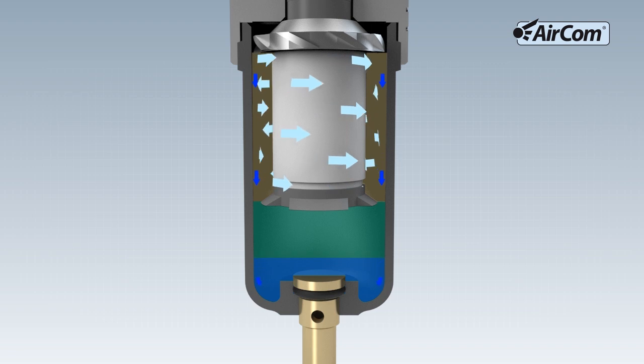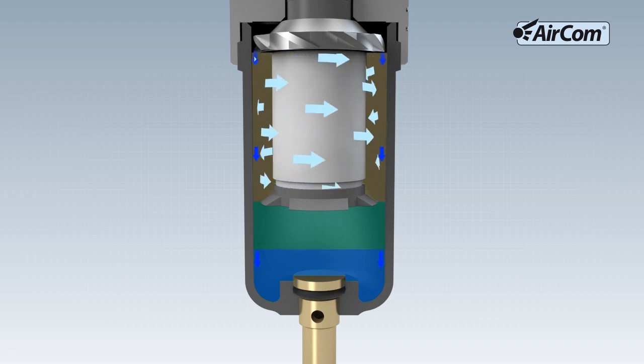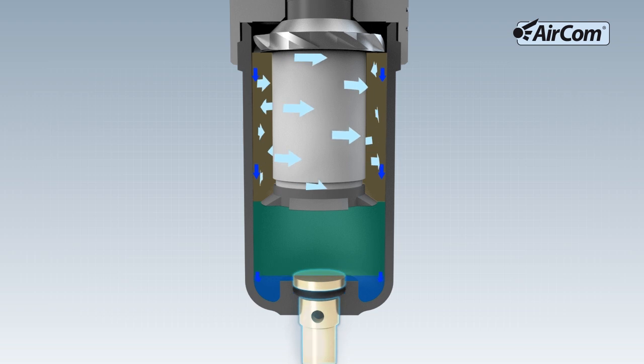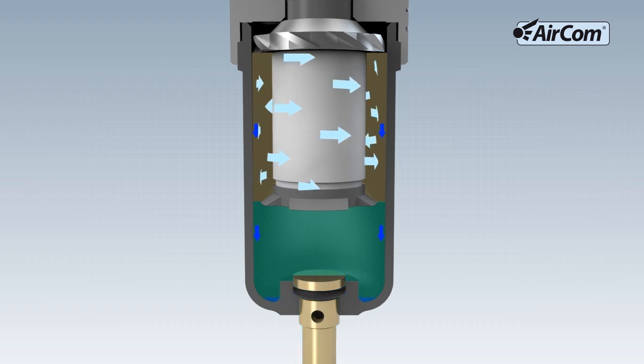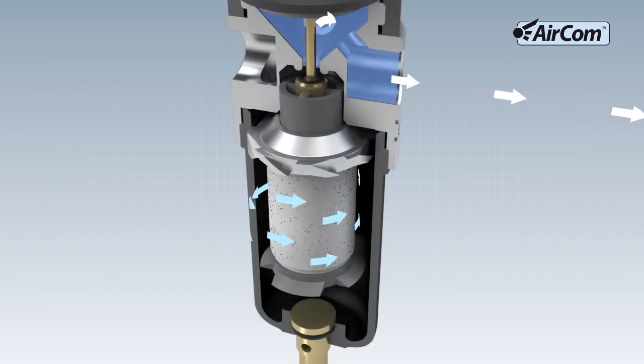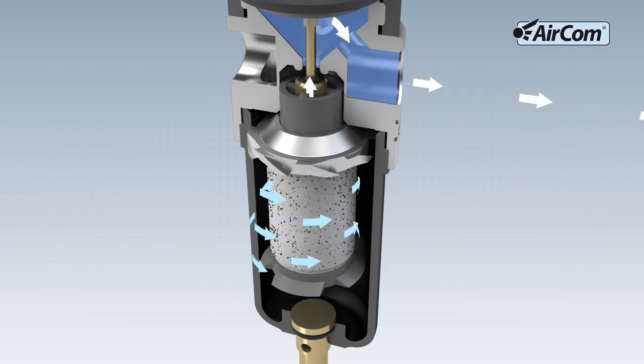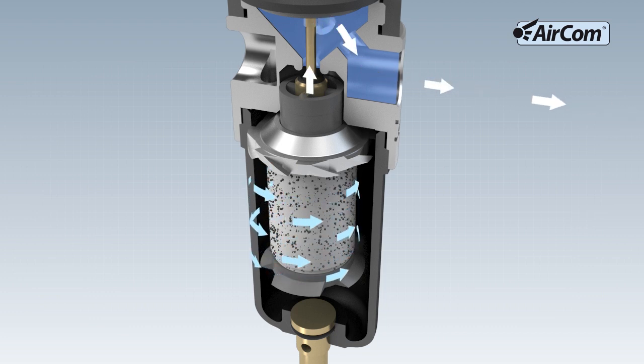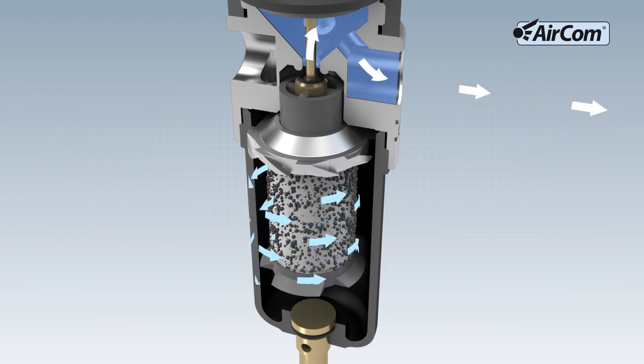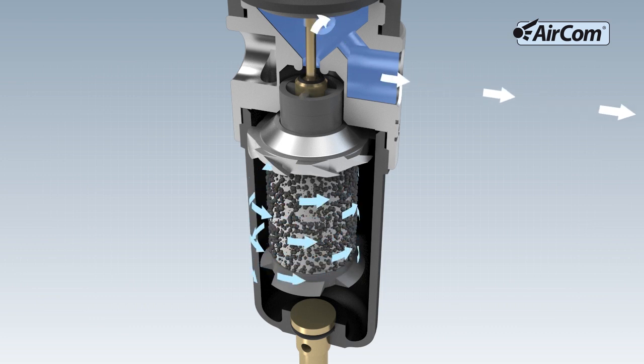The condensate collects in the slowdown zone and can be removed from the filter regulator through a drain. The air from which the condensate has been removed now flows through the filter element to remove the remaining dirt particles, before arriving at the valve seat of the regulator.